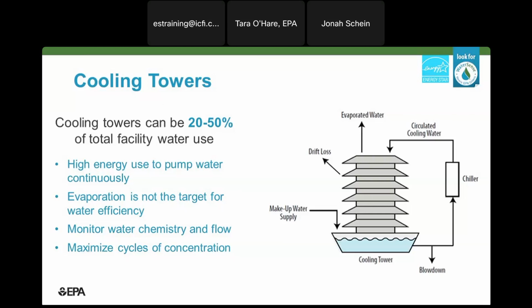So these are the things we target in cooling tower efficiency: eliminating drift loss, minimizing the amount of blowdown we have to do, controlling for conductivity, and thereby limiting the amount of makeup water.